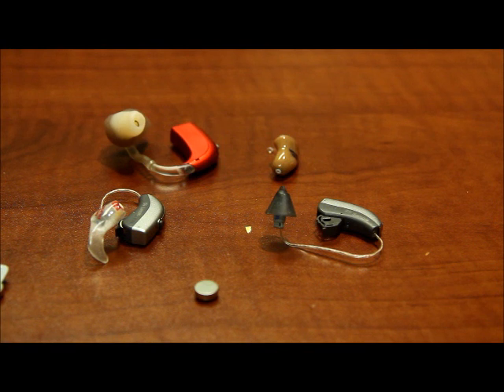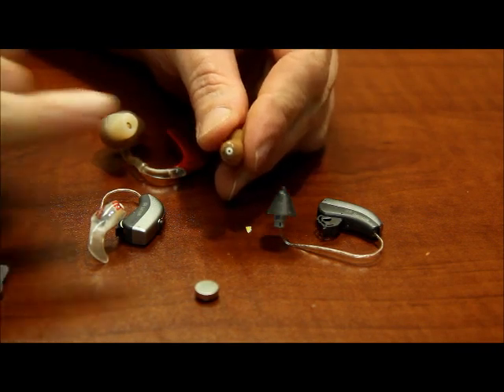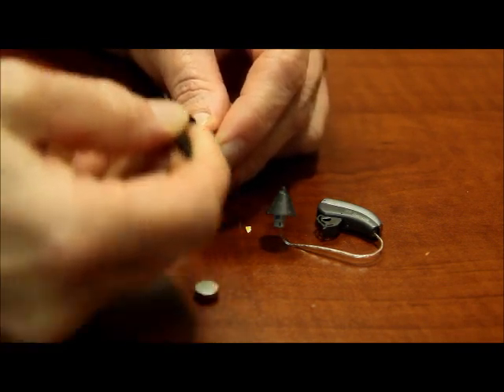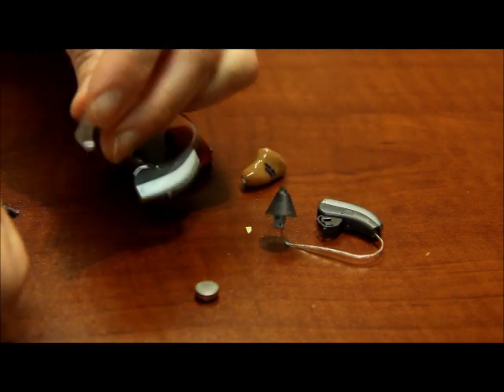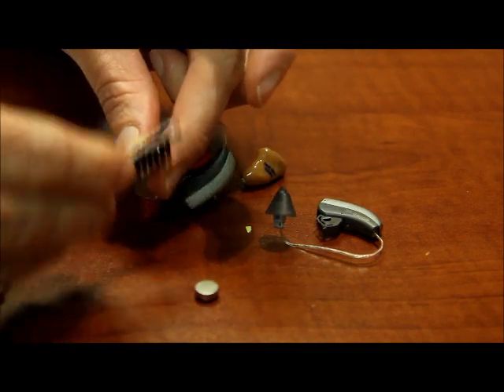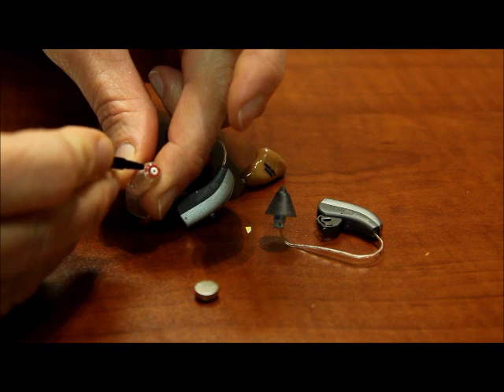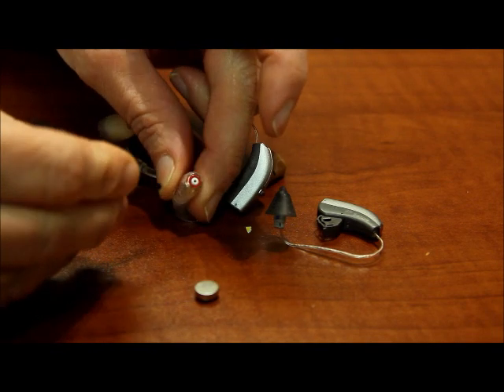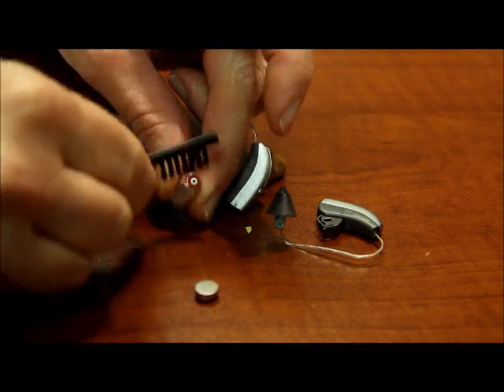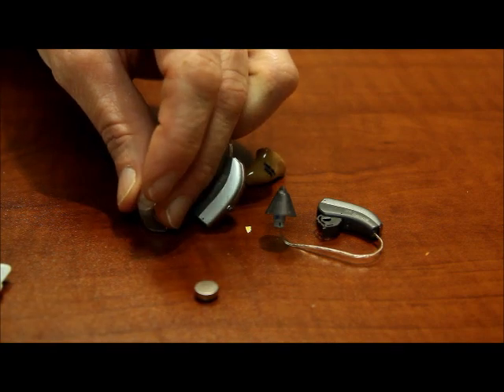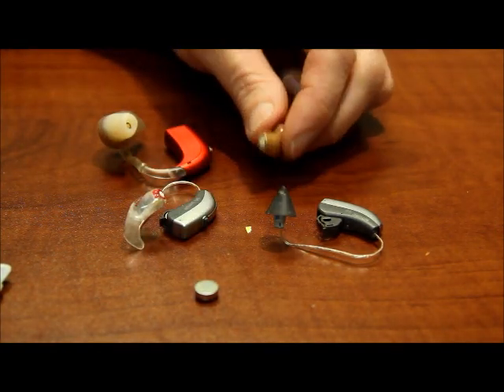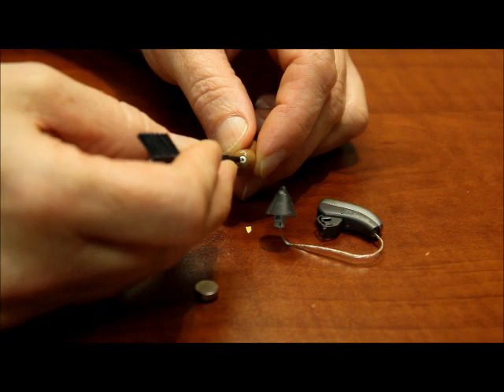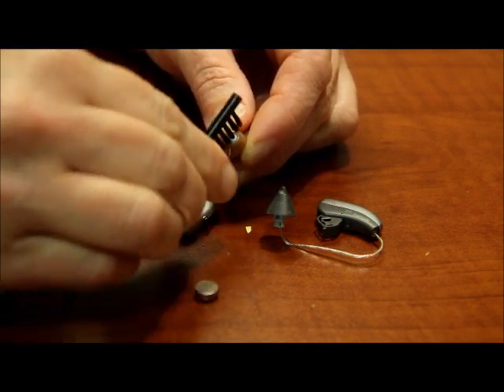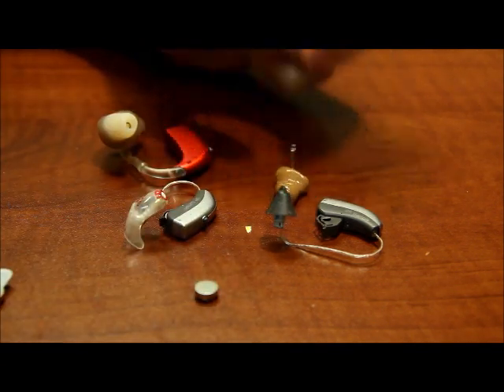If you're sure that it's not the battery that's causing the problem, the next thing to check would be the no wax or wax stop. It's the little white piece at the end of the receiver. You'll see it at the end of an in-the-ear hearing aid, at the end of a receiver in the ear hearing aid. It's that little white piece there. We have a video on how to replace that piece. You can check that out for specific instructions on that. That little piece collects wax and prevents it from getting into the receiver and requiring repairs.